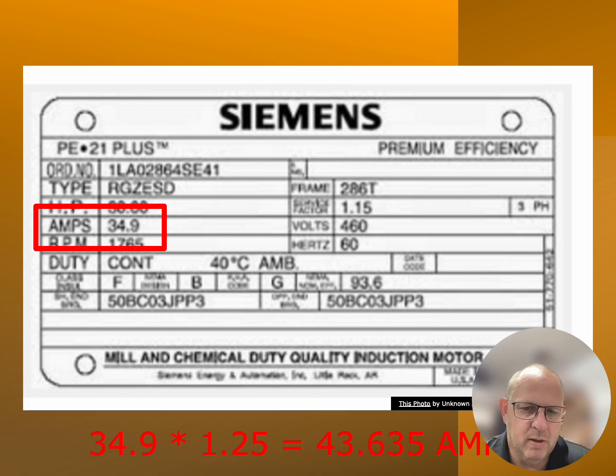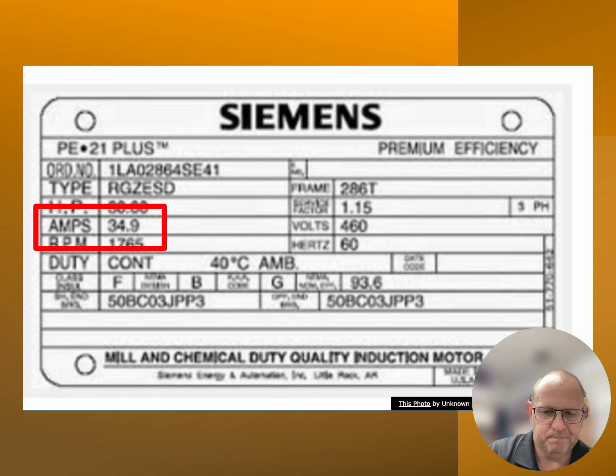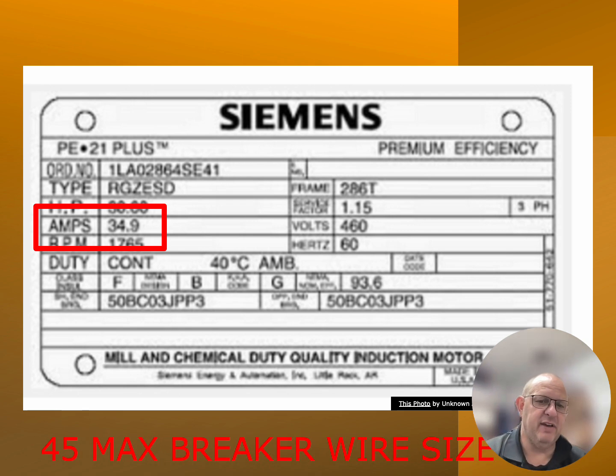If it doesn't give me minimum and maximum breaker sizes to put on this particular unit, then I have to use the National Electric Code to come up with a particular amp draw on this unit based on a corrective factor given to us by the NEC, and that's 1.25. So 34 amps times 1.25, we end up with 43 amps of electrical current that I have to account for on this particular unit. So what size breaker am I going to use for that? I'm going to use a 45 amp breaker. Okay, a 45 amp breaker is going to be used to protect the wire that is on this particular unit.